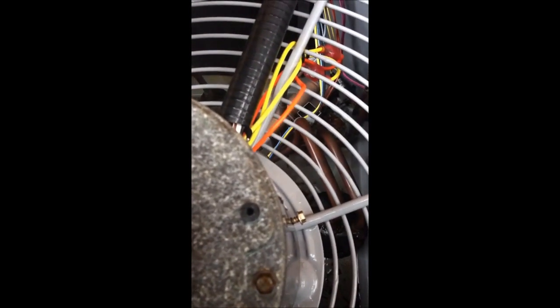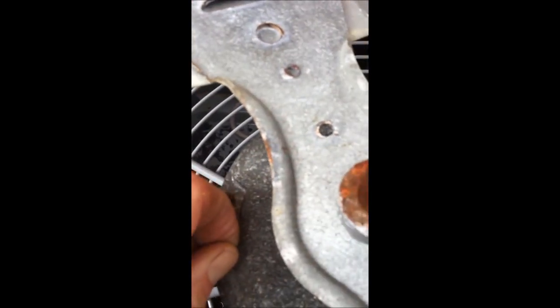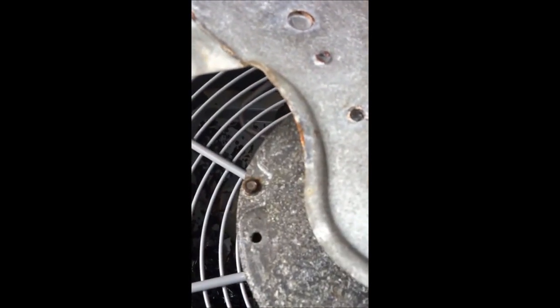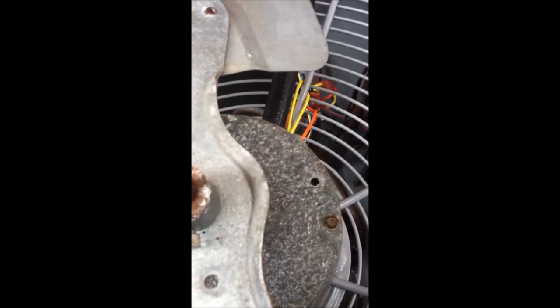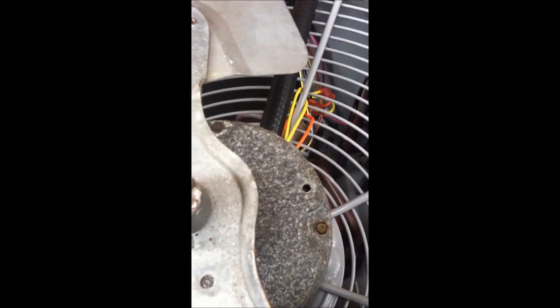And this allows condensation and moisture to drain out of the body of the motor. That one's been removed. And they should be removed when they're installed. And this will prevent moisture from collecting inside the housing and then ruining the bearings on the condenser fan motor.